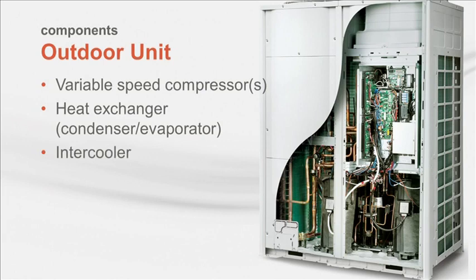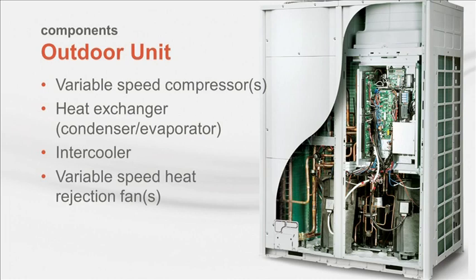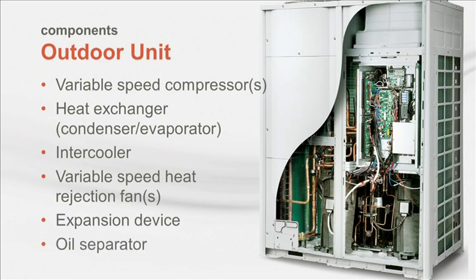An additional heat exchanger, or intercooler, is provided to increase subcooling in the cooling mode and heat output in the heating mode. The heat rejection fans may be variable speed, multi-speed, or staged. An expansion device is included to lower the refrigerant pressure before the outdoor coil when operating in the heating mode. An oil separator is installed downstream of the compressor to reduce the amount of oil leaving the outdoor unit. This allows the system to run at very low loads and accommodate long refrigerant line lengths.